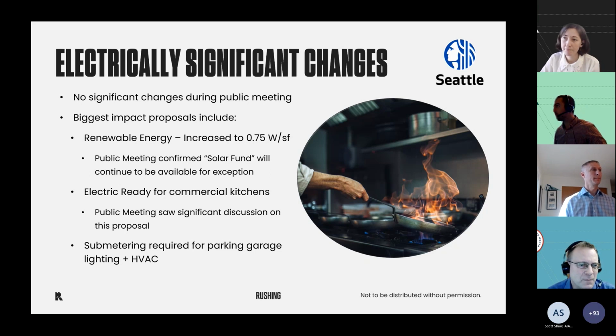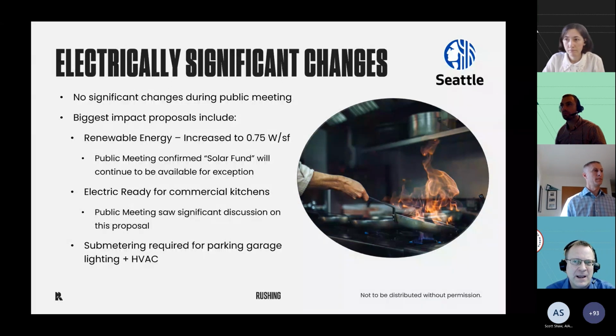Getting back to electrical readiness for commercial kitchens, the focus in Seattle recently has been on energy use in buildings, but not really on one facet that's more operational. The new requirement is shaping up to require us to create service capacity and distribution for future electrical equivalent to the gas MBH capacity for cooking. Even if today it's gas-fired cooking in a commercial kitchen, that will still be allowed, but we need to have the service capacity and a panel either in the kitchen or a nearby adjacent space.